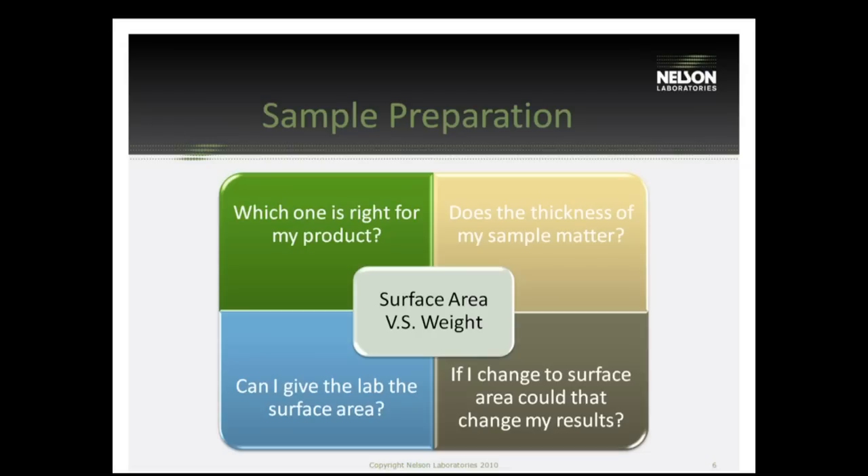Recently, if you use weight as a ratio of your device to volume, you have to be prepared to justify why you did so to the regulatory agency you're submitting to. Most of the time, weight is a worse-case test, especially with dense materials — metals or very thick plastics — where you'll get much more volume of media per device by weight than by surface area. If at all possible, use surface area as a ratio for determining how much sample you need. The reasons to use weight would be for pellets, powders, or something like Velcro — items with huge surface area that are very difficult to measure.